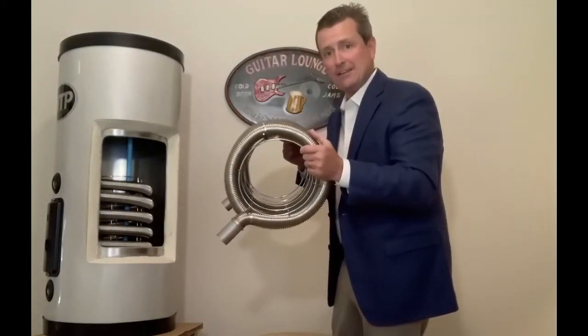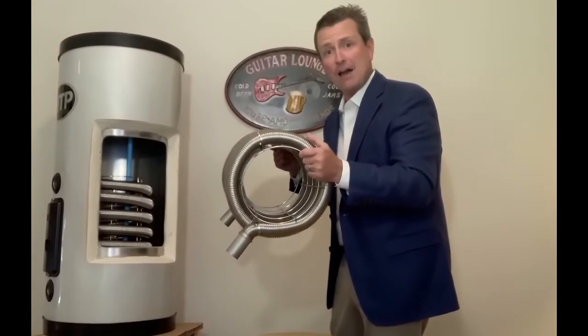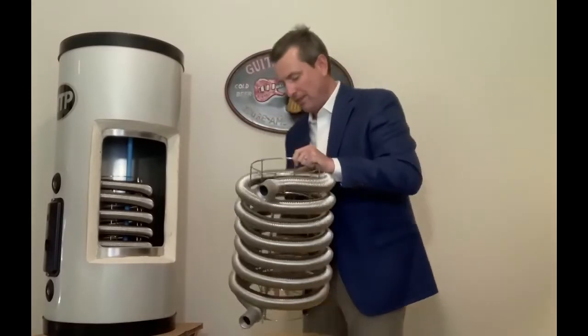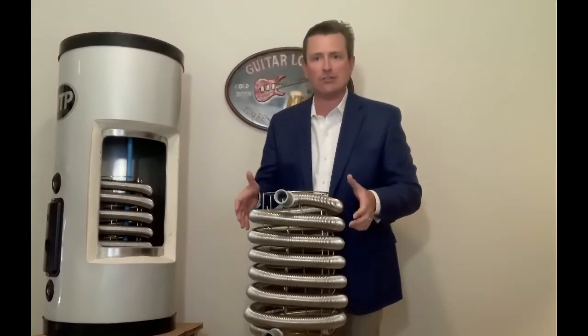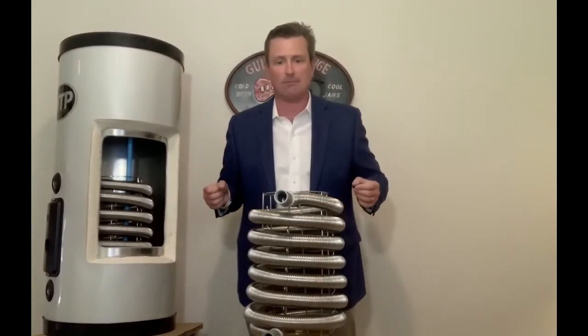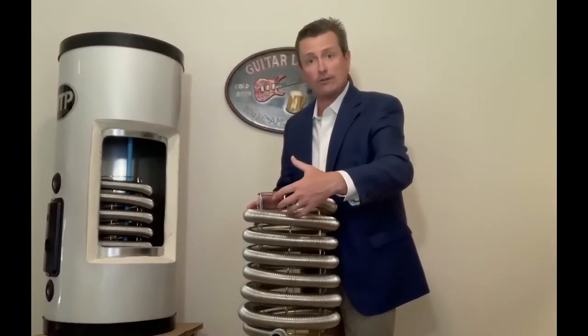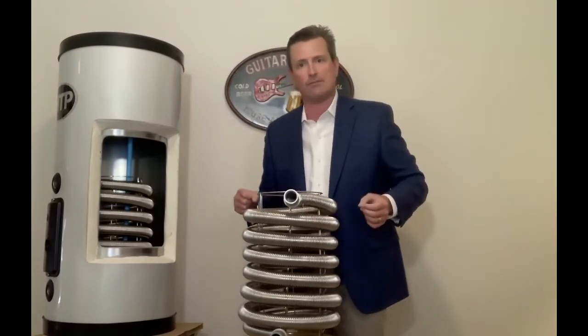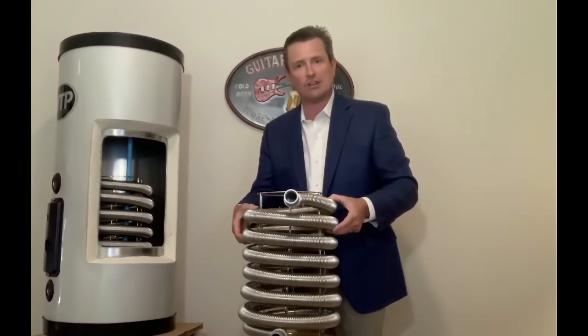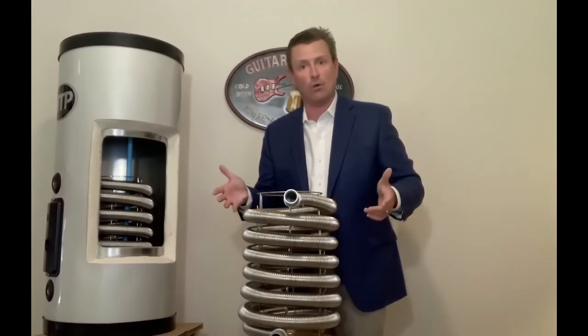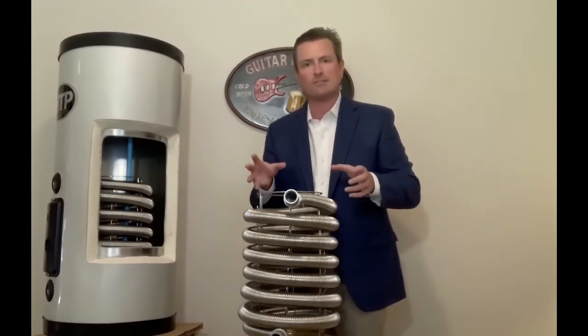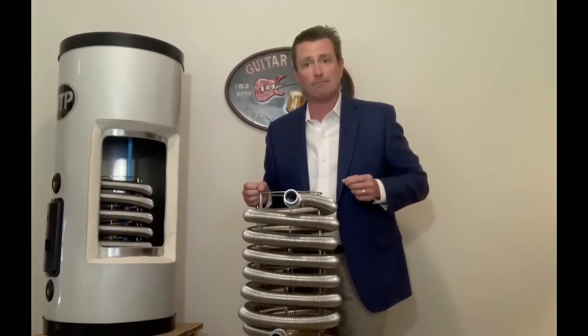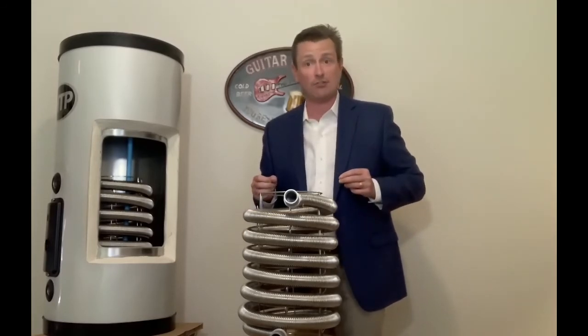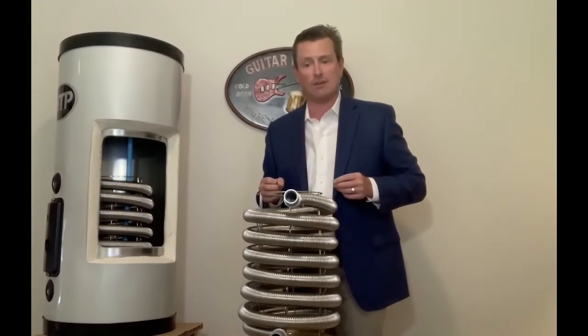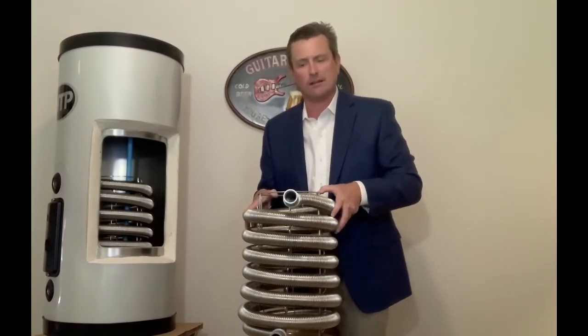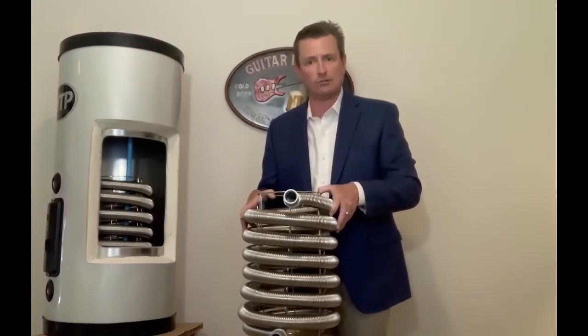As we look inside here, we're going to see that the heat exchanger is actually wrapped around a stainless steel cage. And what this does is it allows the heat exchanger to expand and contract as it's heating up. So think about this. As we're bringing in hot water into the heat exchanger and we're surrounding it with that cold water that's coming in from the street, this cage allows the heat exchanger to actually flex. By doing so, we're going to shed any mineral deposits that may get on top of the heat exchanger over time. This is going to increase both the efficiency and the life expectancy of the coil itself, because I'm not going to be trying to heat up through that extra debris. I'm going to have a clear path from the heat exchanger to the water stream.